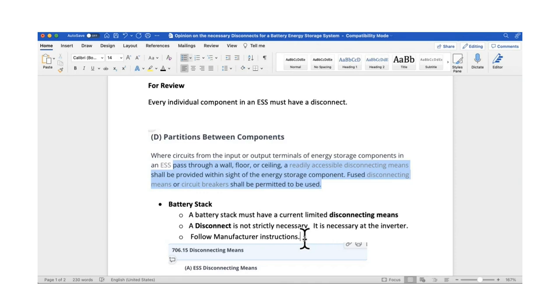Most of the language in 706 is for the energy storage system. And so they kind of look at it like the batteries and the inverter are all the same thing in a way, like that's the energy storage system. And so if you look at that and you turn off the inverter, the way that it's listed and made to work, you're not going to have dangerous currents coming off of the battery there. I believe that it's going to be inside of that UL 9540 listing, that once you turn off the inverter, it signals that battery to not just have 400 volts coming at you. And that would be 400 volts approximately. A lot of times these batteries are around 400 volts, whereas it is going through a DC to DC converter.